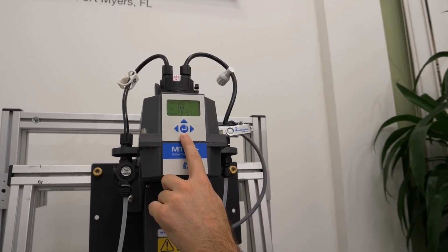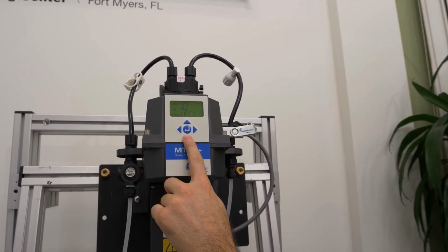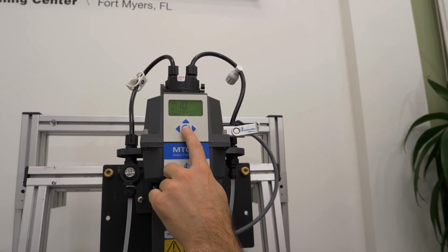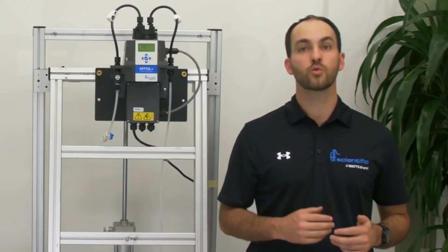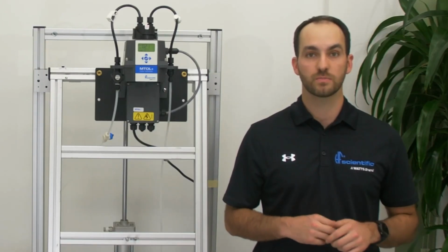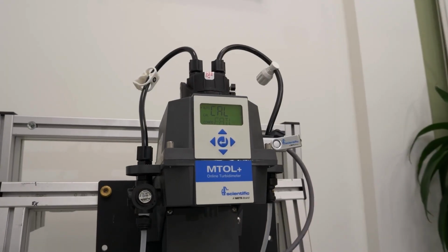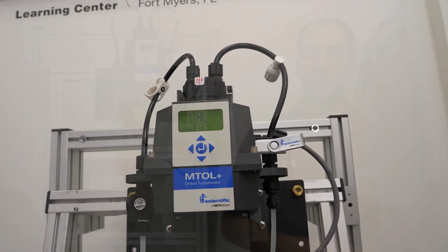The ranges are delineated by the top number of the calibration range, 10, 100, or 1000. Once the new range is loaded, the analyzer will display Cal Fail, and a new calibration must be performed for the analyzer to work.